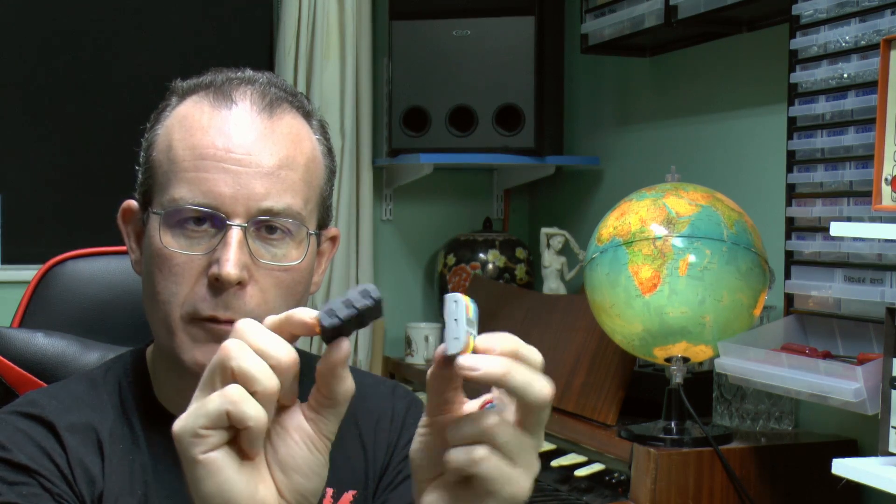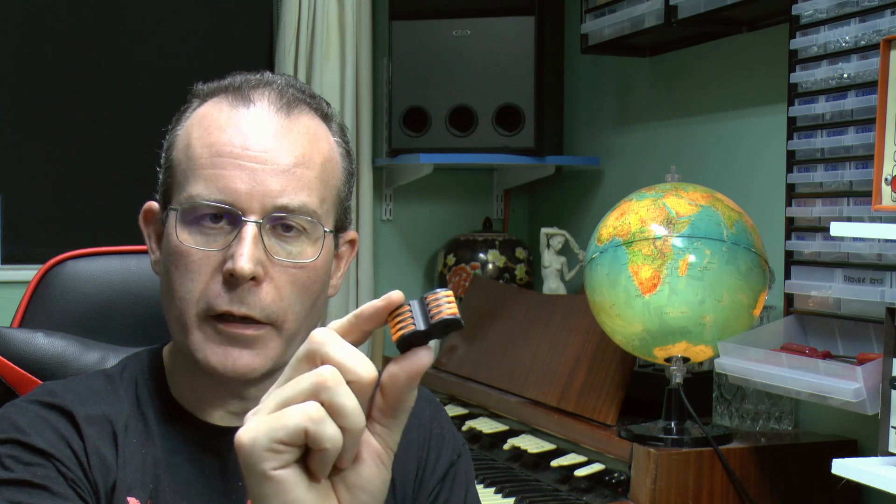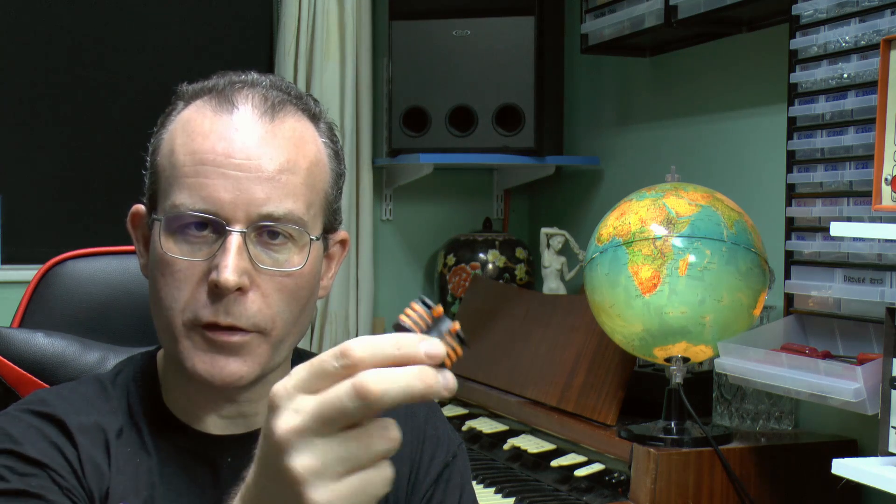So there's a look at a few of these Chineseium connectors. And they're not actually terrible. I mean, they would probably do the job and no doubt work as intended. So the big problem with these things is that if you're going to buy these in from China yourself, if anything goes wrong with these and it causes someone else to burn down, then of course you are the person who's liable for that, not the manufacturer in China, which is why I wouldn't recommend using these in an actual installation. Certainly going to need to get the proper ones, because in the case of those, if there's a problem with it and it proves to be the product at fault, then the manufacturer of course is the one on the hook for that. And generally you would expect things from any reps from the manufacturer to be consistent in their actual quality and whatever else.